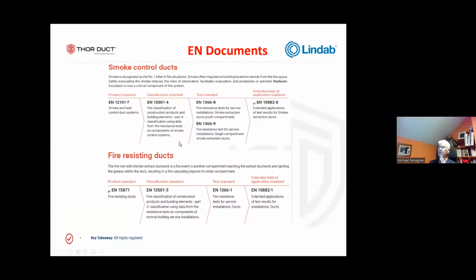look at that. Very simply put, there are two types of fire ducts. Ducts are used to ventilate buildings, but in a fire they have two purposes, two types. One is a smoke control duct. So the idea of a smoke control duct is you're going to take the smoke out of the area in the building that's on fire, and very often bring it through the rest of the building to get it outside. We use smoke control dampers with smoke duct to determine how we control the evacuation of smoke. We understand why it's so important to get the smoke out. That's one particular type of duct.